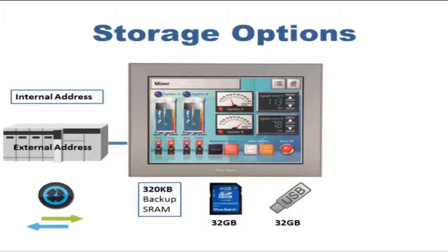Data is stored in either the local battery-backed SRAM memory or in an external memory device. The internal memory size is model dependent, ranging up to 320 kbytes. This equates to 316 samples of 512 word values or 81,000 samples of one word value. Many GP4000 terminals support SD and SDHC memory cards up to 32 gigabytes. Every GP4000 terminal supports USB memory devices, also up to 32 gigabytes.